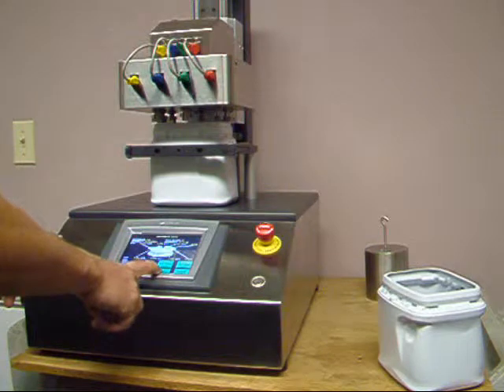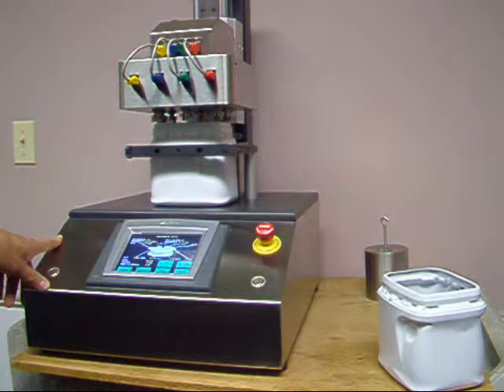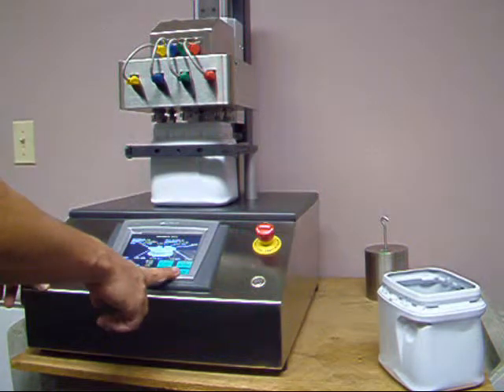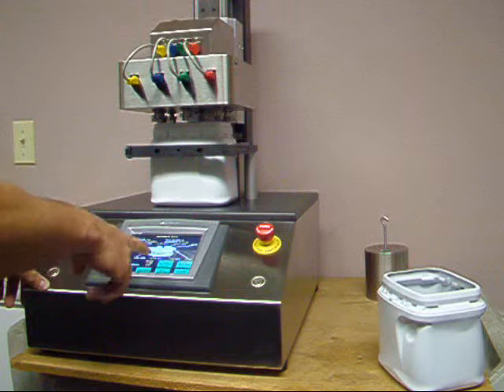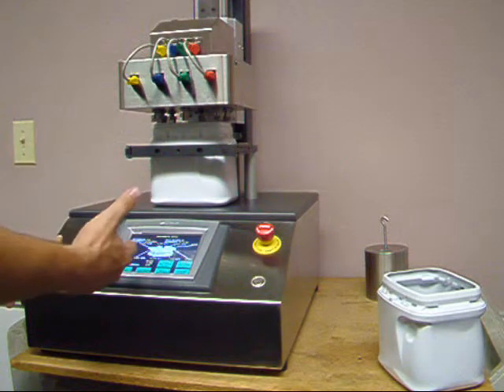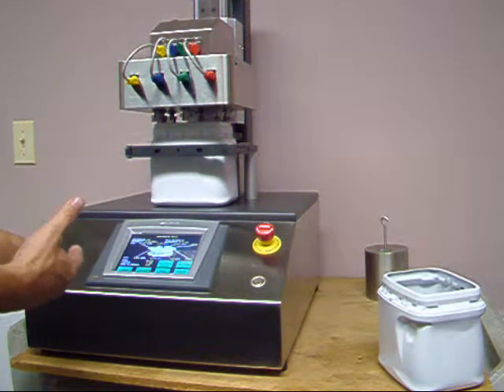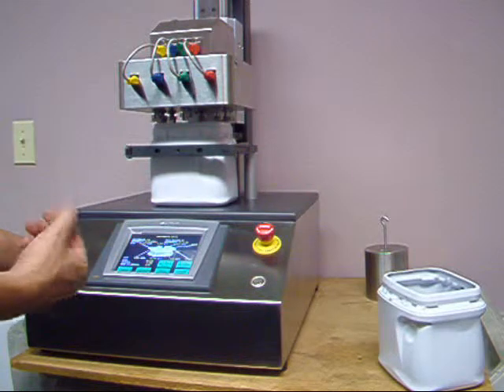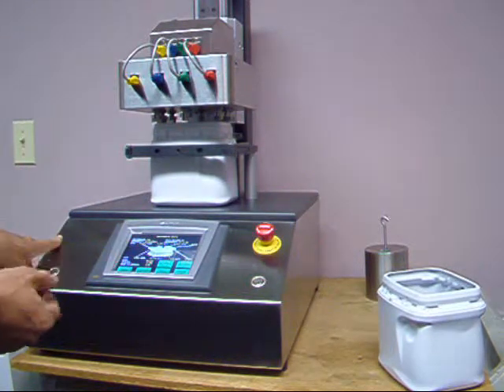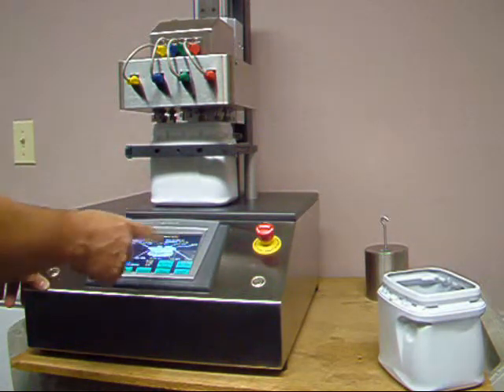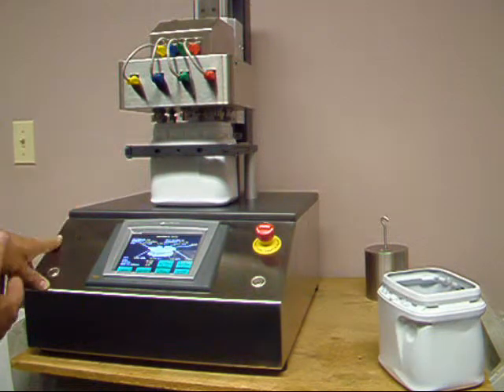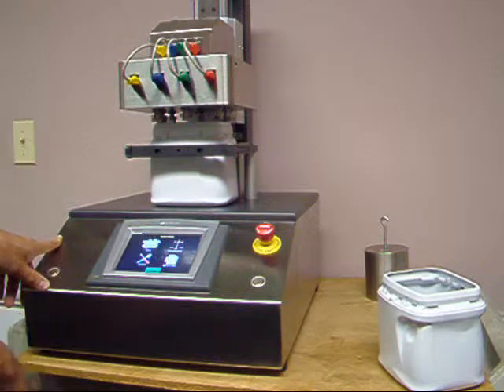It will store 500 records, 500 of the last 500 tests, and then you can clear the table on the screen. You can send all of the data that's stored in the data table or in the memory to the PC, and this will send out the peak values, or you can just transfer one record at a time by pressing the appropriate keys here.